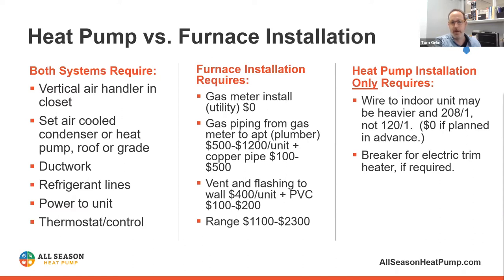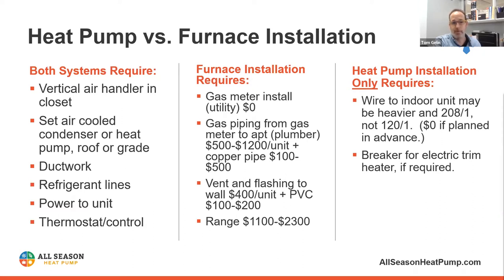With a furnace, the utility company installs a gas meter — they generally don't charge for the meter itself. But you do have to run gas piping from the meter to the apartment. For a two-story walk-up that may not be terribly expensive, but you have to buy the pipe and spend the time running it. That can be anywhere from $500 to $1,200 in labor, and the copper pipe might be $100 to $500, so somewhere between $600 and $1,700 for gas piping.